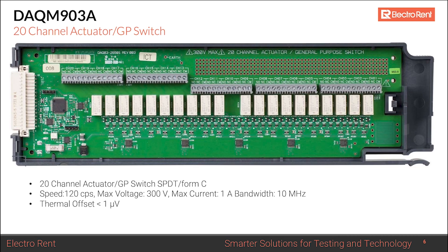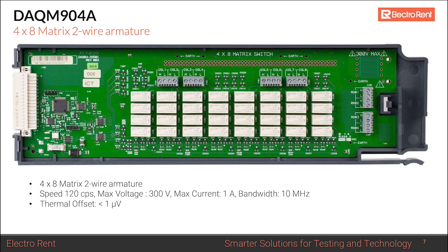The DAQM903A has a low thermal offset but no reference junction, so it cannot be used for thermocouples — it's strictly a general-purpose switch card. The DAQM904A is a 4-by-8 matrix with hard relays, useful for signal routing. You could route four power supply voltages to eight board points, or connect four instruments to eight different signals. It supports 300 volts and 1 amp with a low thermal offset, but again has no reference junction for thermocouples.